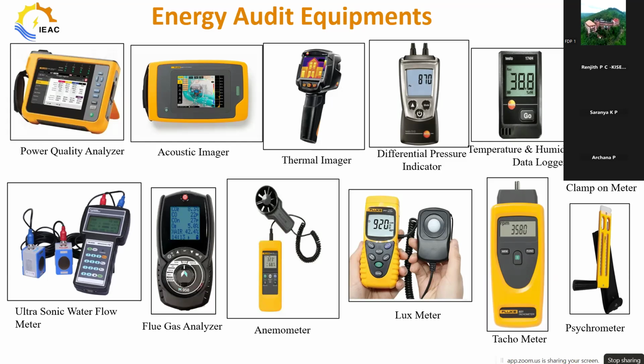For the safety audit, we mainly use thermal imagers, differential pressure indicators, and temperature and humidity data loggers. This data can also be analyzed in real time on your laptop as well as on your mobile phone. So at the same time, we can get the data instantaneously at timed intervals, either 1 minute or 5 minutes. Temperature and humidity data, that is this clamp meter and others. This is water flow. How much the rate of flow is has to be indicated by the ultrasonic water flow meters.